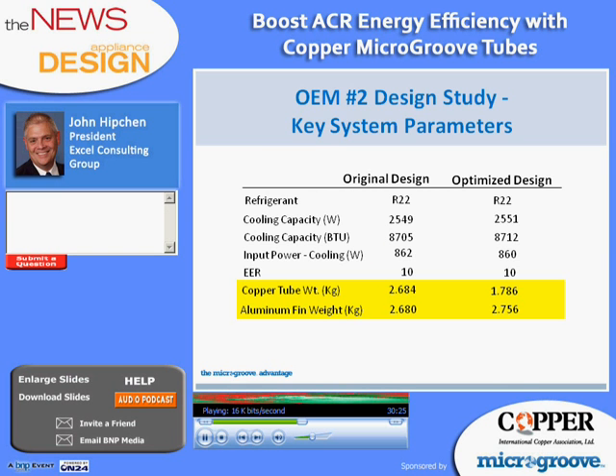The optimized design in this system provides almost a kilogram of weight savings per unit on the copper tubing, but we see a slight increase in the weight of the aluminum fin. And in real life, this manufacturer found the cost savings from the smaller diameter MicroGroove copper tubes to be significant enough to justify proceeding with this design in production.